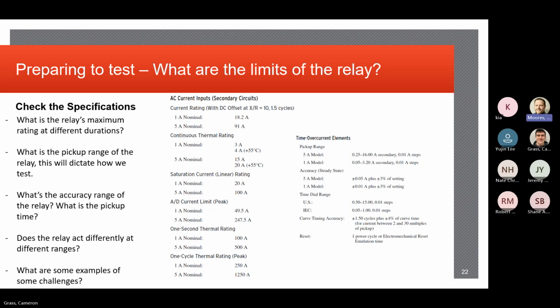We don't want to go make changes to the logic and the hardwired output, the one that's actually doing the tripping. We don't want to mess with that logic. We want to leave it alone. So we just keep changing the elements in the spare output: minimum pickup of overcurrent, minimum pickup of voltage, minimum, whatever, something along the way to help facilitate the testing. Does that make sense? It does. Thank you.